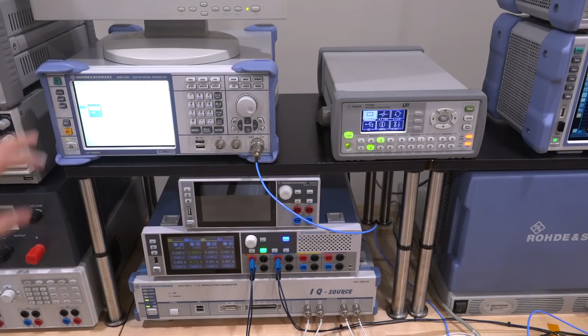So let's go ahead and change the mode of operation, and I can go under the mode button right here. You can see we have several options depending on what options are actually available on the unit that you have purchased. And we have a spectrum capability here. If I click on that, it doesn't get rid of the vector network analyzer. It just adds a new tab, which is the spectrum tab. So all the measurement settings that you have are preserved in this tab. If I go back to the VNA, I get the full-fledged VNA exactly where I left it off.